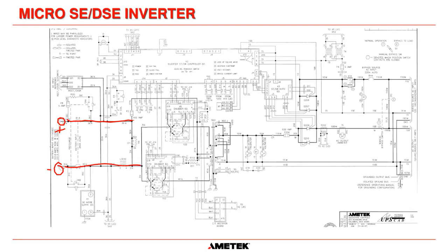We don't have to worry about all this other stuff that's in this part of the drawing here. It's just going to show you where the IGBTs are. So in this system, this is probably a 20 kVA UPS because we've got two IGBTs here. We've got Q1 and Q3 here, and then we've got Q2 and Q4 here. So to get more power, we just put IGBTs in parallel. But then what we're going to do, here's the center point of the transformer here. So you can see the transformer at this point here. We're going to turn Q1 and Q3 on. And once again, just to drive the theory home, we're going to go down here, get to this point here, and we're going to go through this transformer winding back that way to the negative. Okay, so that center point there would be positive with respect to negative there.